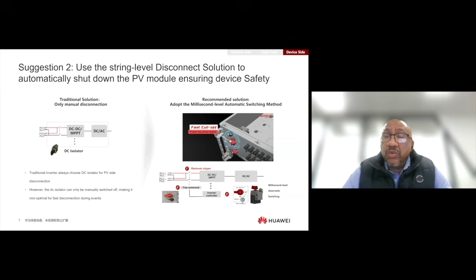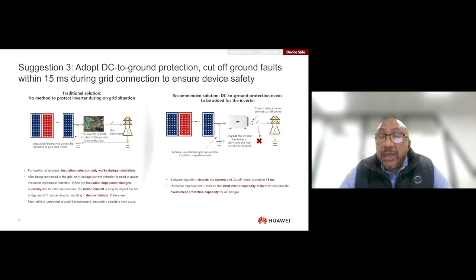Thirdly, we are proposing adopting DC-to-ground protection using the inverter. Typically, you would have insulation protection only during installation. However, after being connected to the grid, insulation impedance changes are typically not easily detectable, due to the inrush current being able to impact the AC bridge as well as the DC busbar directly, causing device damage. What we are proposing is upgrading the inverter hardware with DC-to-ground protection that will limit the inrush current, thereby protecting the modules as well as the AC busbars.